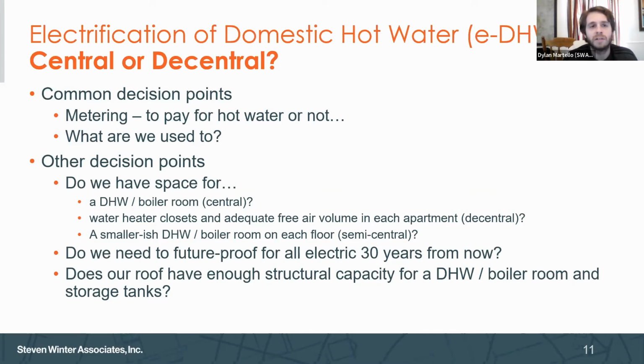For decentralized systems, you have a water heater or heat pump water heater that needs space for its equipment, and if it's a heat pump, it also needs space to pull air and adequate air volume, which can have a big space implication. Or if you're doing a semi-centralized system, you need a smaller boiler room on every floor, which can also have a big impact.